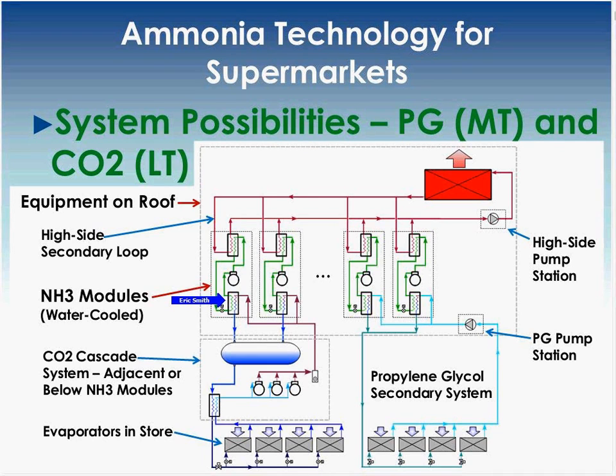So coming out of this heat exchanger that I'm pointing to here is the condensing portion of the carbon dioxide for the low temperature system. So what happens, of course, is the ammonia gets compressed at the compressor, it's condensed at the condenser, and then serves as the condenser for the carbon dioxide. This is what is known as a cascade system. So you can see where I point with my arrow here, a thermal expansion valve, and that's the pressure drop to create the cooling effect.